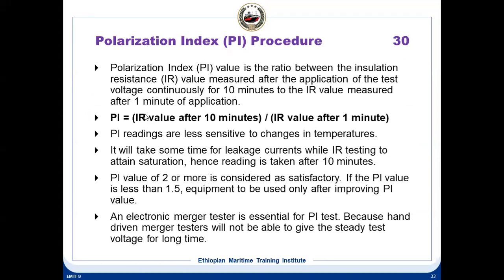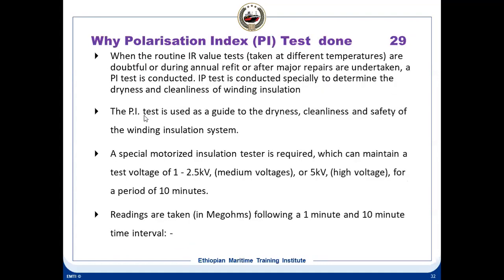2 to 4 is good. Above 4 is excellent. Less than 2 is questionable. Less than 1.1 is a very dangerous situation. So the polarization index test is a very important test. It is carried out especially on high voltage equipment. It is used to gauge the dryness, that is the main thing, dryness or moisture, cleanness, and safety of the winding insulation system.